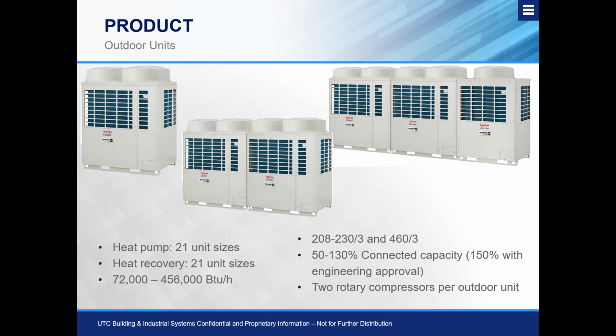So with these outdoor units, for each individual outdoor unit, we have two rotary compressors, which have the dependency of equal runtime. And also we have protocol boards that look at compressor runtime so that we can balance the total runtime between compressor 1 and compressor 2, which generates a longer lifespan because they see equal wear.